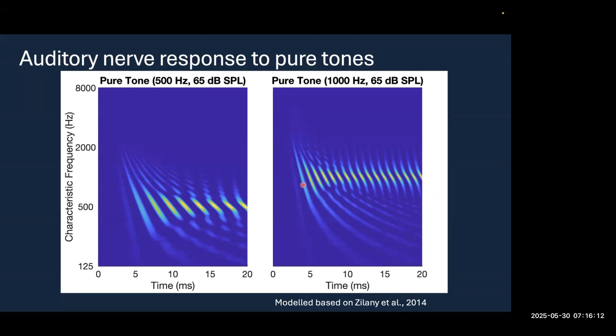Now, in contrast to that, the conventional cochlear implants generally do not use precise timing. So if I made a similar figure, but showing the stimulation pattern coming out of a typical cochlear implant for a 500 hertz tone and for a 1000 hertz tone, you see, oh, hey, the place of stimulation, the electrode that is firing changes. So it's doing a good job of conveying tonotopy, or as good of a job as possible if you only have 22 electrodes in this current spread, but it's doing a pretty good job of conveying that. However, there is no information in the stimulation timing.